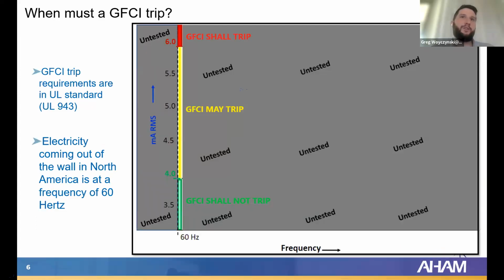When must a GFCI trip? So these are the GFCI trip requirements that are in place today. And GFCI trip requirements are governed by UL 943. That is the UL standard for the GFCI, whether it's a GFCI breaker or a GFCI receptacle, they all have to comply with these requirements. And something to keep in mind before we look at this diagram is that the electricity coming out of the wall in North America is at a frequency of 60 hertz. So it makes sense that all the GFCI trip requirements are at 60 hertz.